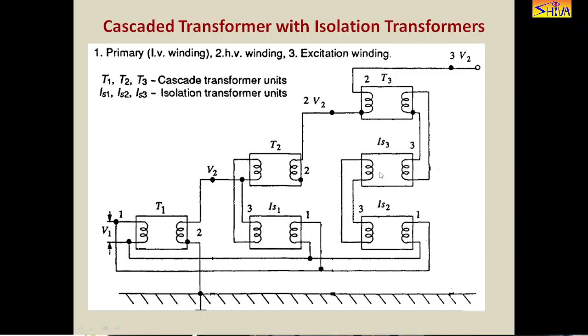Isolation transformers have a voltage ratio of 1:1, so whatever is the input voltage to the primary winding, the same is the output voltage of the secondary winding. This acts as the excitation winding for the second stage as well as the third stage. The same primary voltage is given but it is not fed through the first stage of the cascaded transformer, so the previous drawbacks of large excitation requirement and loading of the first unit are avoided.